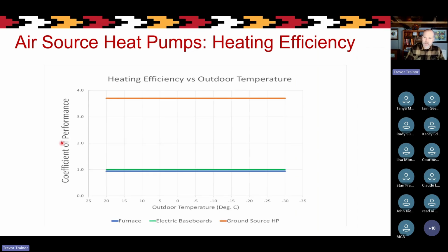And so now I have to change my scale when I start looking at a ground source heat pump. So now instead of talking about efficiencies, we're talking about coefficient of performance. Whereas the baseboards and the furnace acted with a coefficient of performance around 1, a ground source heat pump can have a coefficient of performance of 3.5, 3.75. And because it's below ground, it's not really affected by the outdoor temperature. So it can maintain that no matter what the outdoor temperature is. Again, that's for the ground source heat pump.